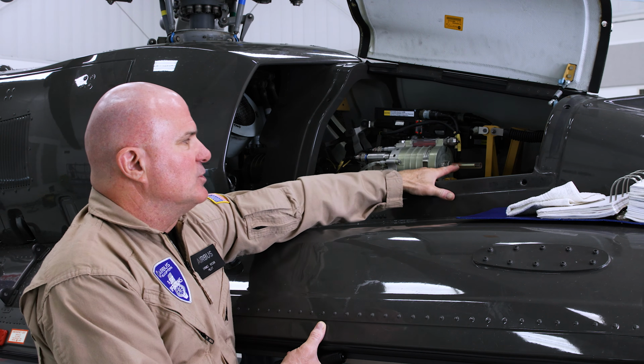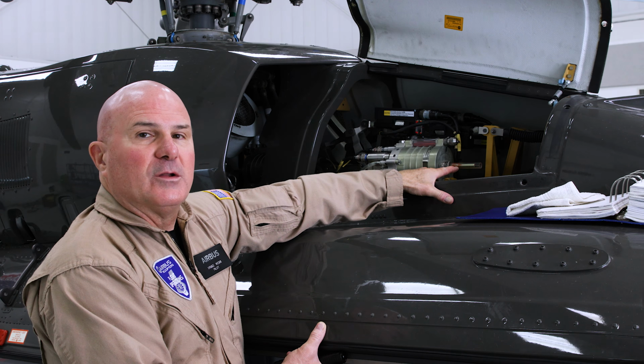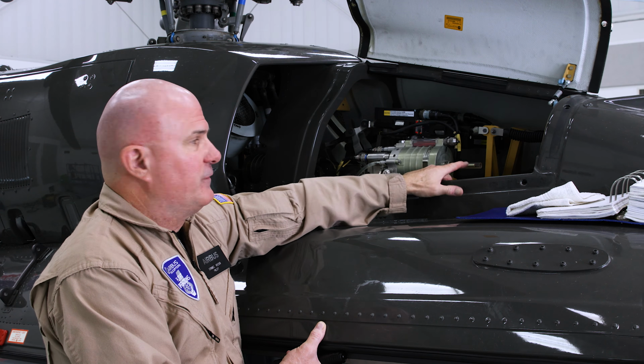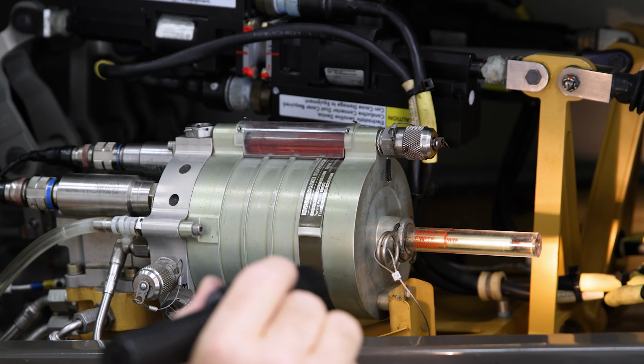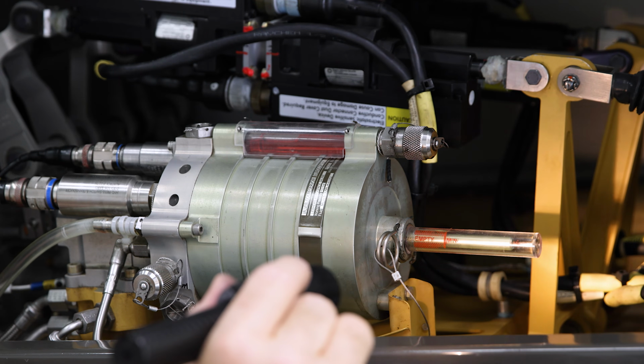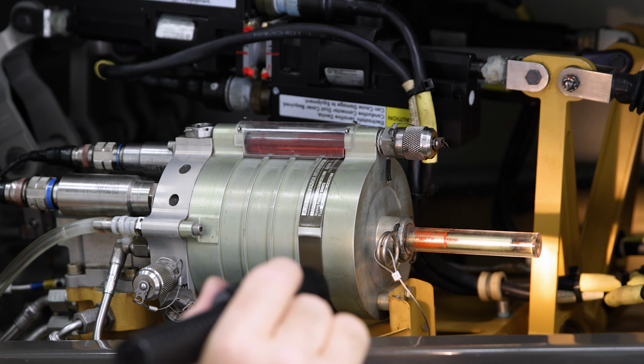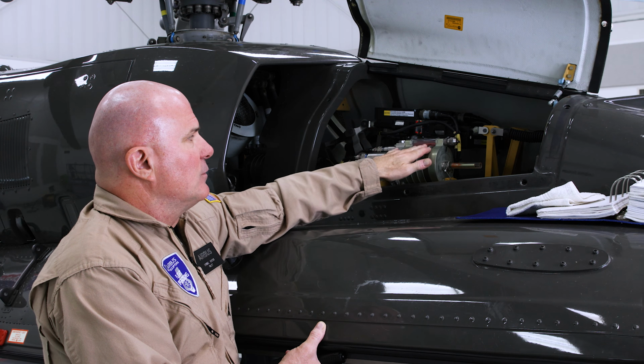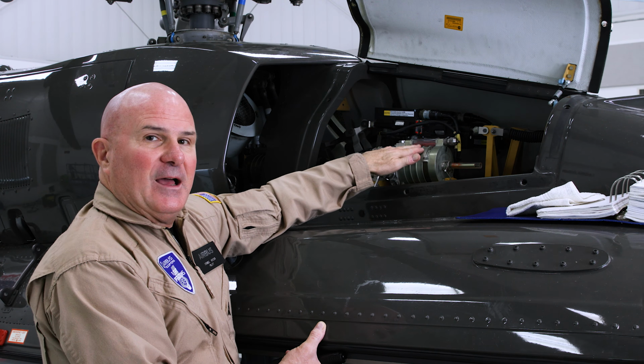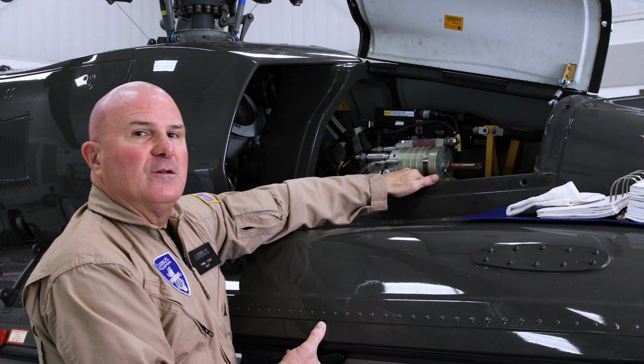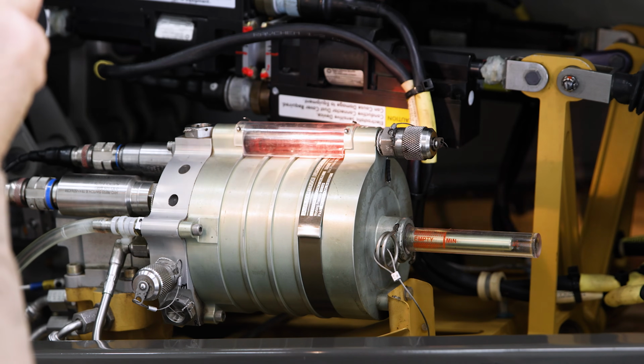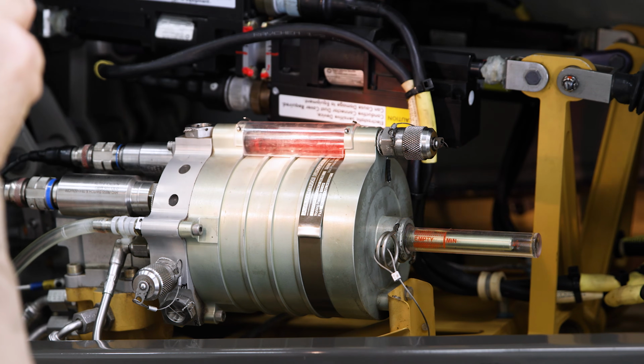We would check to ensure the fluid quantity is sufficient by ensuring this pin is extended beyond the min line. We would also check that the sight glass here is at least 50% filled with fluid, which indicates there is no air in the system.